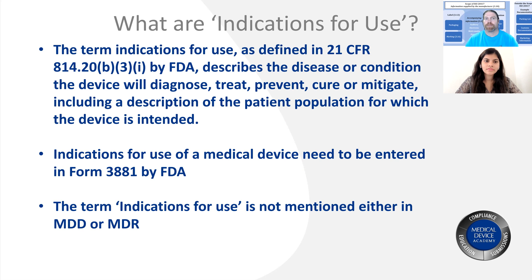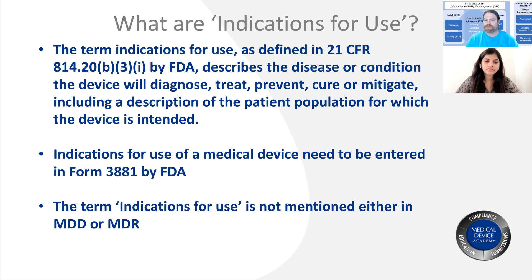If you read the regulations, they define what indications for use is. When you submit a 510k and it gets cleared, the FDA publishes a form letter saying you've been cleared. They also publish form 3881, which defines your indication for use. If you also have a 510k summary, it will have a direct copy of that indication for use statement. It never shows the intended use.